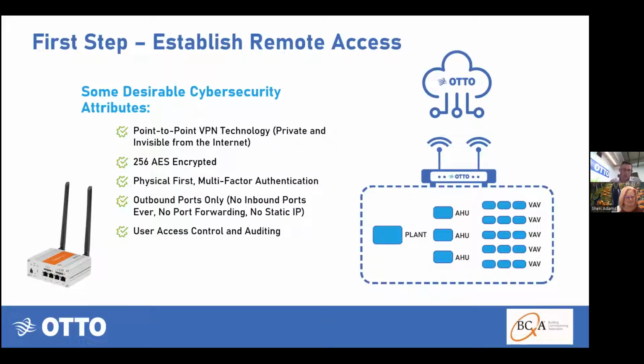Outbound ports only, from an IT perspective, means the communication originates from inside the network. If you open your web browser to Google, you've sent a request out of your network to get a response back. You're allowed to receive a response to your query, and that does not require inbound ports to be open. It's a bit of a confusing misnomer in the IT world. Outbound ports only doesn't mean we can't communicate back, it just means the IT network administrator didn't need to open an inbound port for us, and we're still able to do overrides.